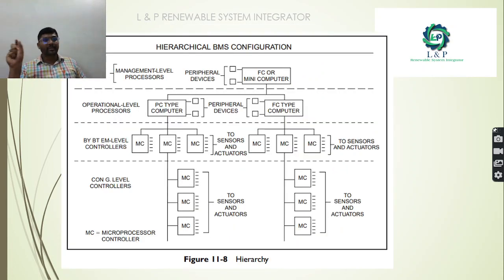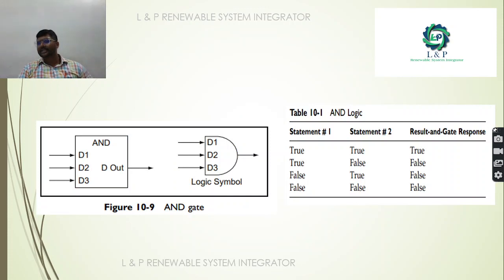If you are going for a hierarchical BMS configuration, most importantly we will have management level processors. It can be mini computers or it can be servers. Normally we will have operator level workstations, which are in another category. Third, next to it, we will have the controller level, where master controllers will be. They will be connected with many sensors and actuators. We will also have another category, slave controllers. In those, only input and output modules are present; the CPU will not be there. The CPU will be only in the master controller. From the master controller the command is provided, and the entire input and output are connected to the master controllers. So this is a typical hierarchy of a BMS configuration. In this also we are using many logics.